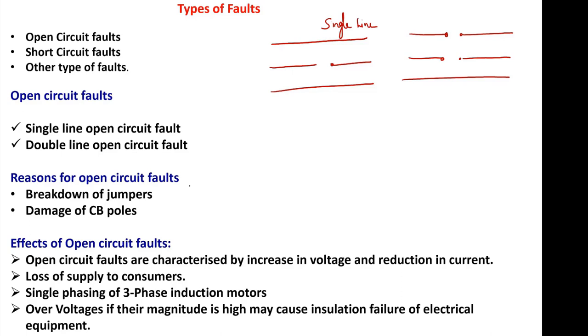What are the reasons for open circuit faults? The jumpers connecting one tower to another may get disconnected. In hot summer season, there is huge heat, so thermal expansion will be more, and sometimes at high tension they may get cut. Due to uneven expansion and contraction from seasonal changes, the jumpers may also get cut.